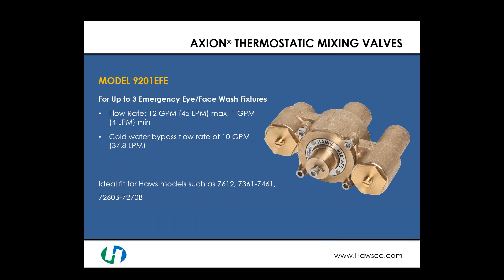Moving to another version of the 9201EFE — also designed for up to three emergency eye face wash fixtures — the maximum flow rate here is 12 gallons per minute with the same minimum of 1 gallon per minute. The key difference is the internals allow a cold water bypass of up to 10 gallons per minute. You get the same good mixing features, but in the event of a hot water failure, this valve has significantly more bypass flow at 10 GPM compared to the previous valve's 3.8 GPM. It is an ideal fit for the same compatible models.